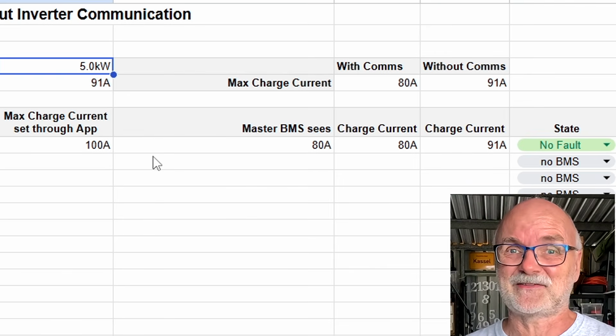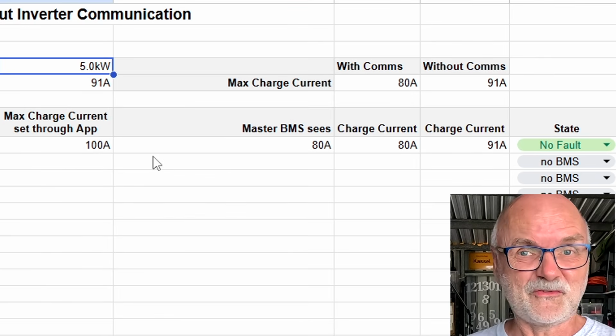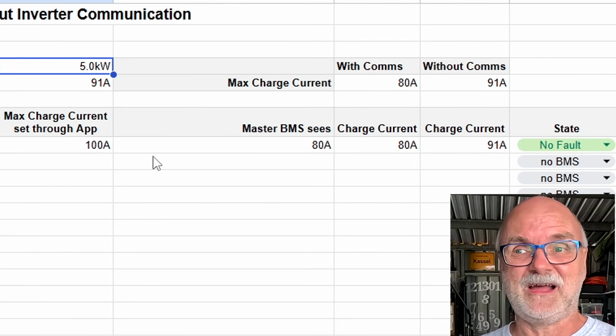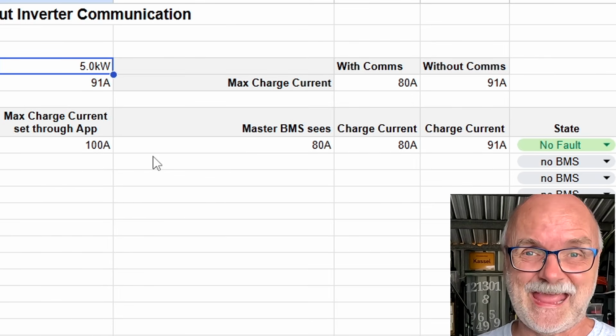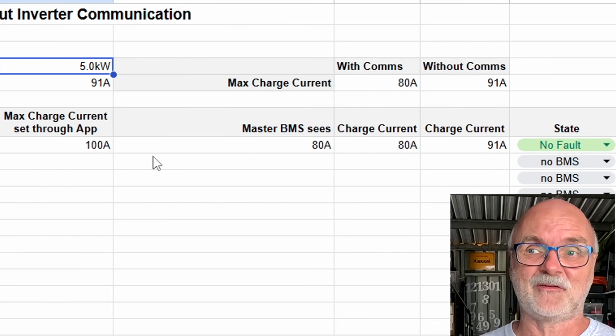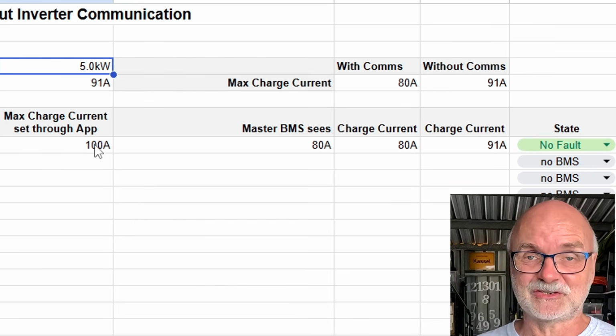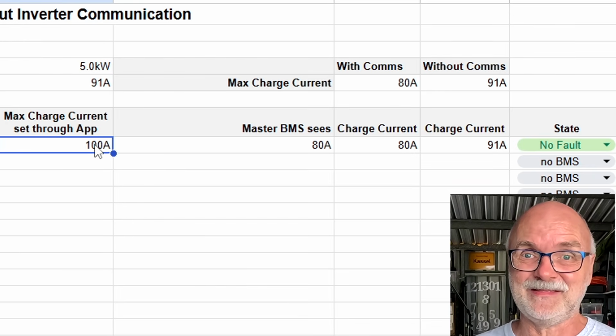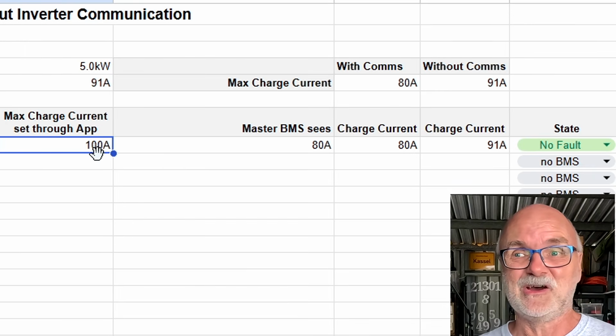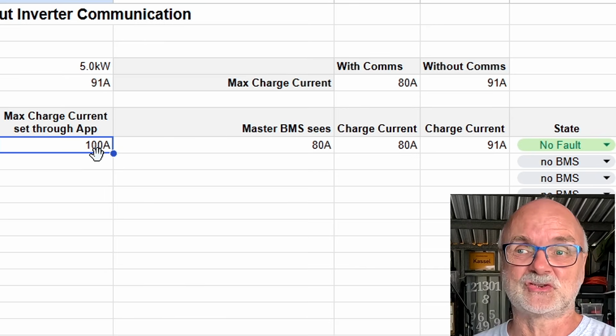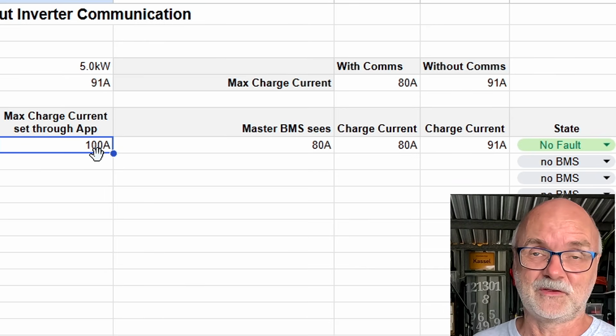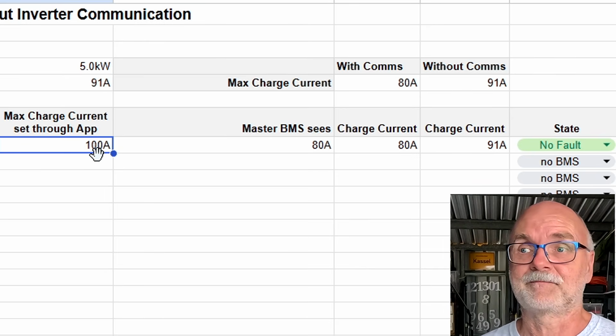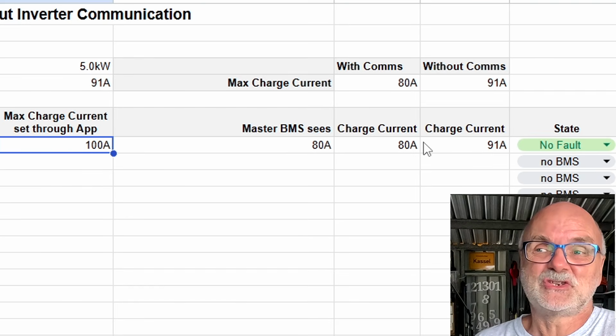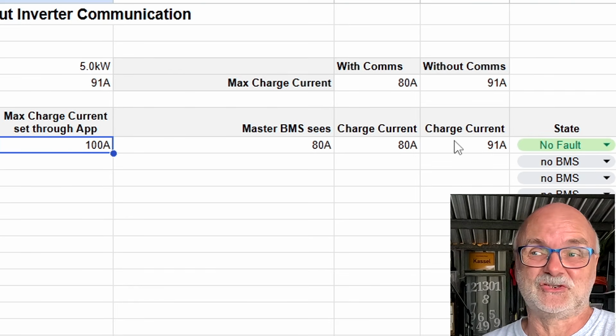Well, this depends solely on the fuse you have on the circuit breaker and also, of course, on the cabling you are using to connect your battery. So you need to set your maximum charge current in the BMS for each of your batteries according to the cable dimensions and also the size of your circuit breaker and/or fuse. So here in this example, no issues with or without communication, right?